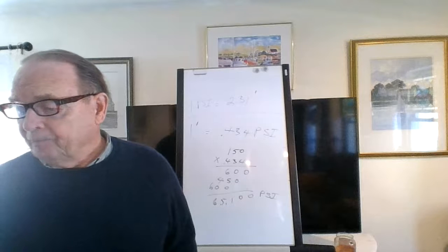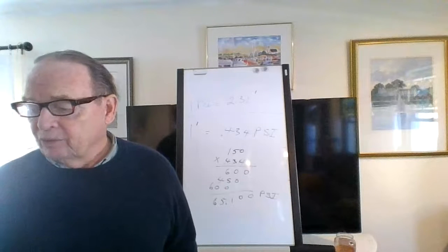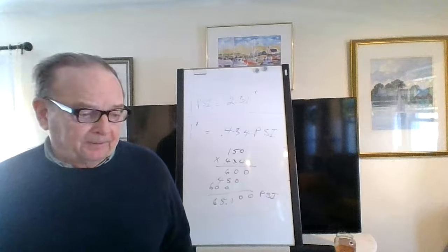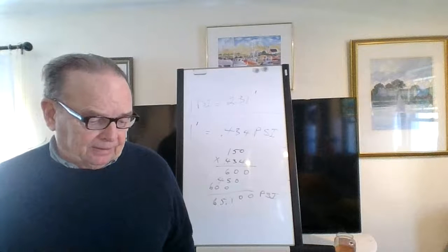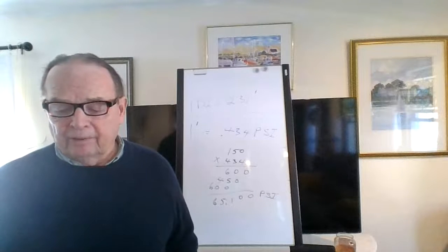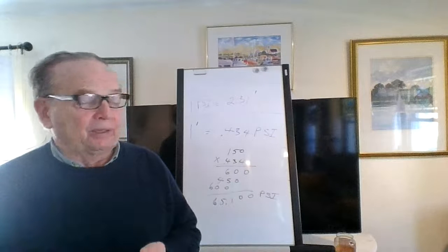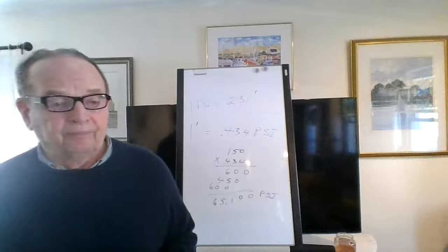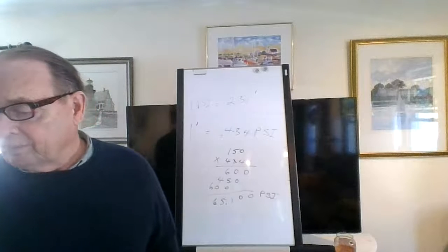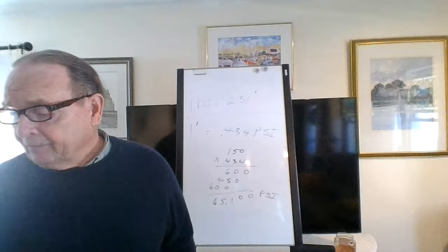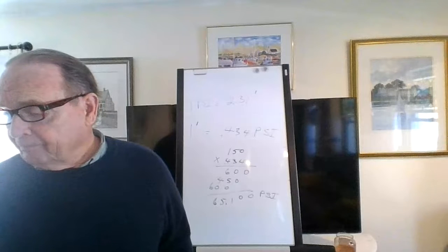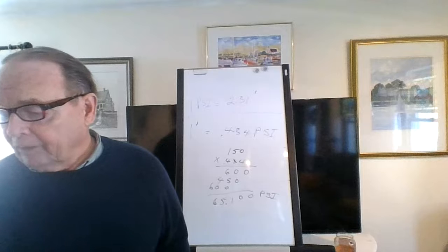Now, if you don't want to put a pressure reducer on, you can put an X-Trol. It's actually about the size of a baseball, and you screw that on near the appliance that's causing the problem. If you have an appliance that's causing the banging, there's ways around it. Okay, let's leave that alone.